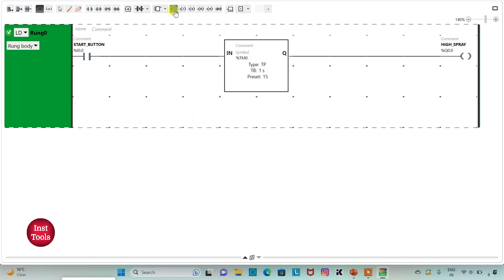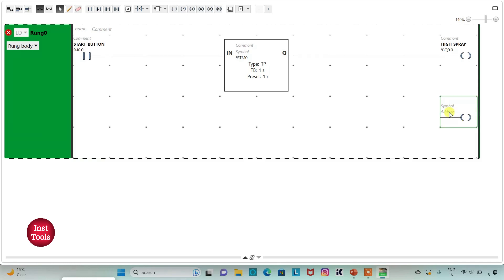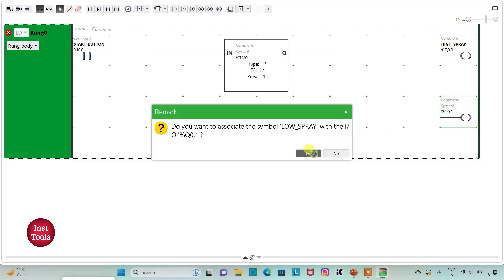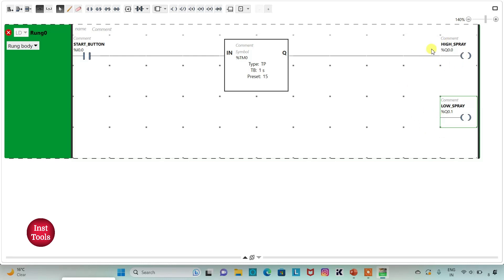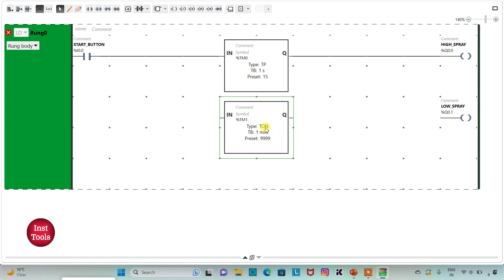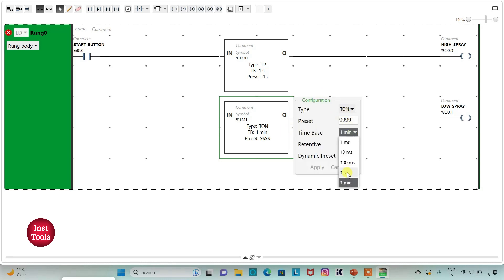Then I will insert one more coil and assign the address Q0.1, adding the symbol 'low spray'. Low spray should come after high spray, so I will use a TON timer to introduce a delay. I will change the time base to 1 second and set the delay to 15 seconds, changing the preset to 15, then click apply.